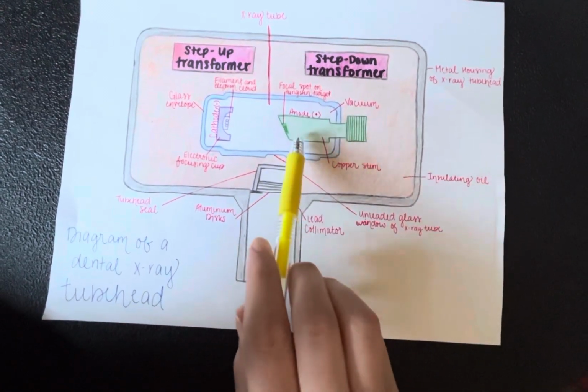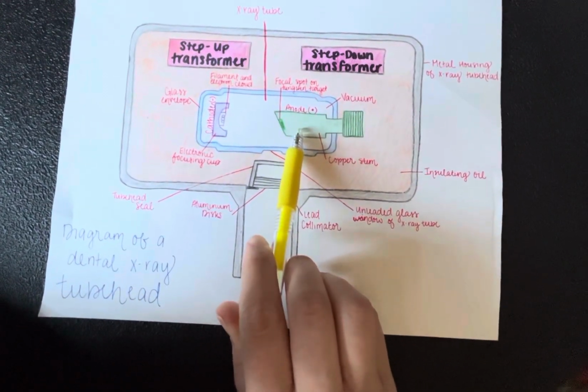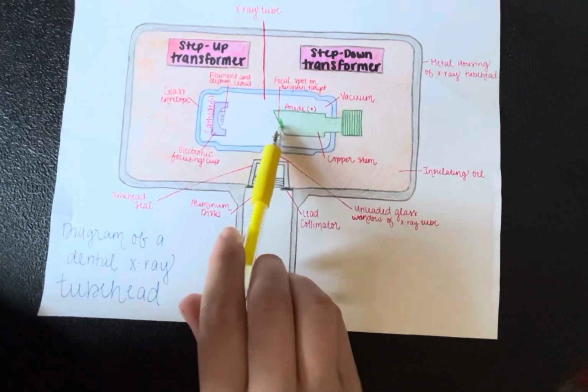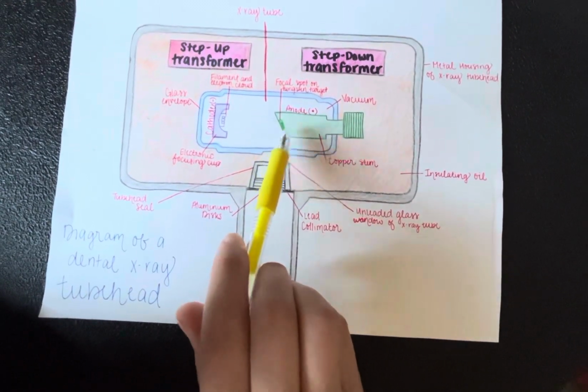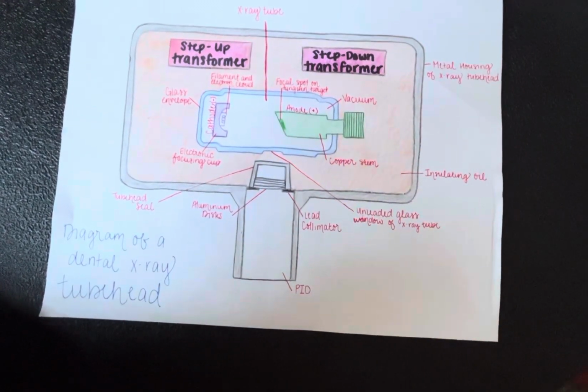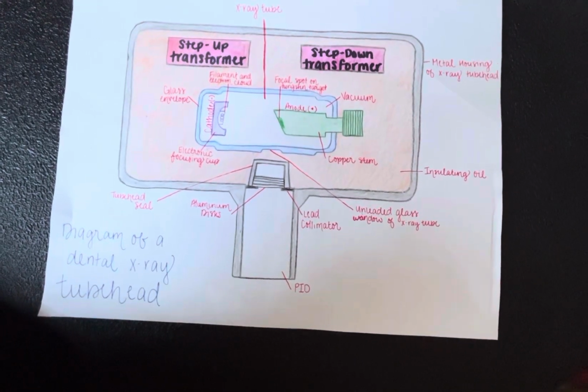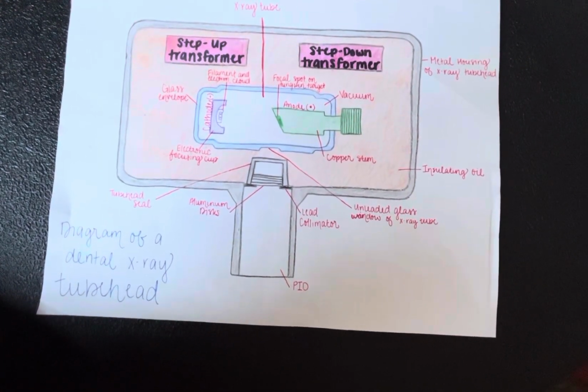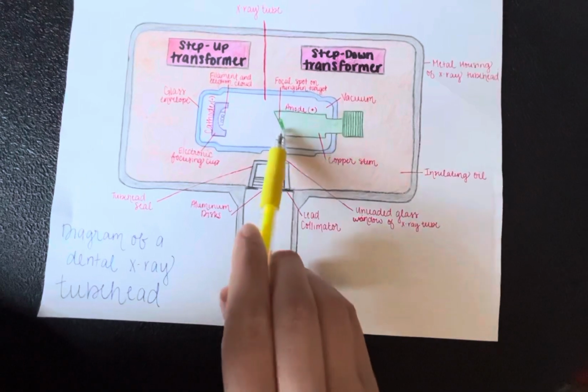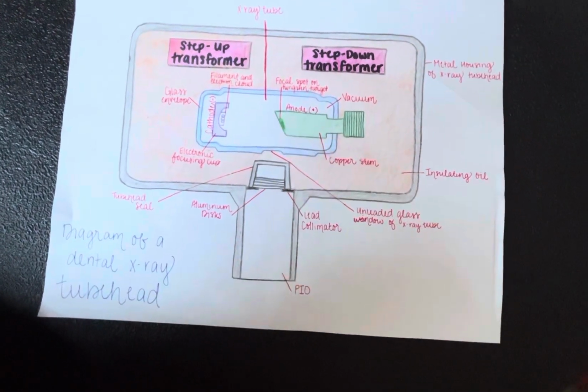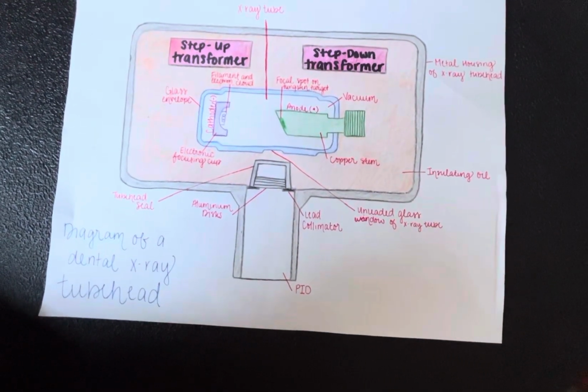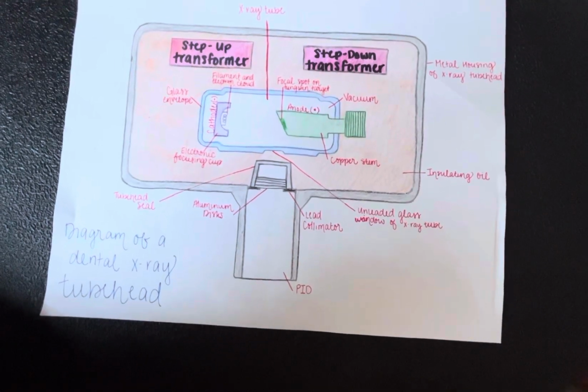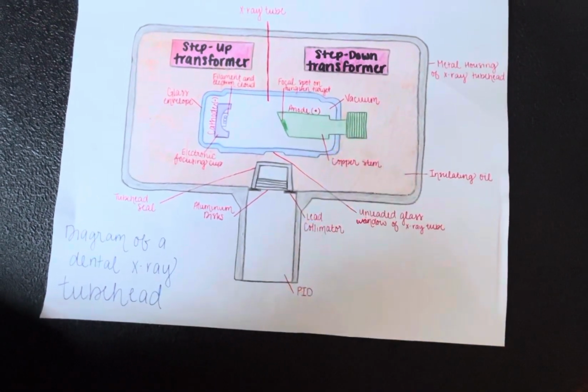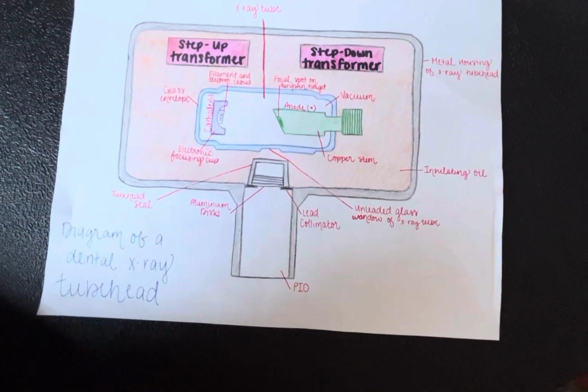The anode is a positive electrode consisting of a wafer-thin tungsten plate embedded in a copper rod, and the purpose of the anode is to convert electrons into X-ray photons. The tungsten target serves as a focal spot and converts the incoming electrons into X-ray photons. The copper stem dissipates the heat away from the tungsten target.